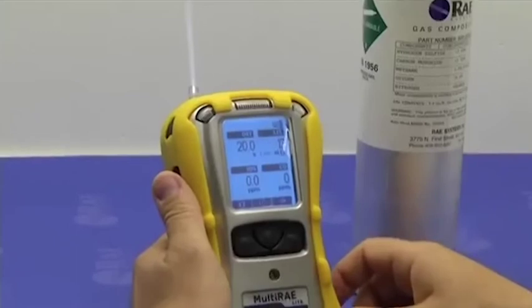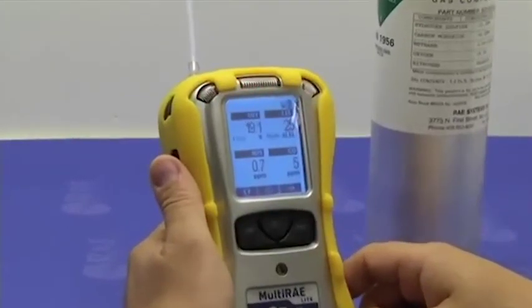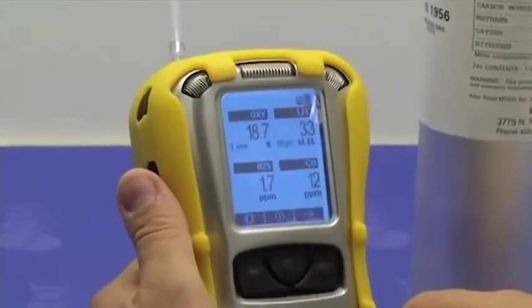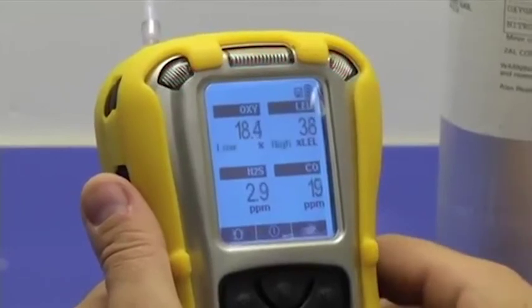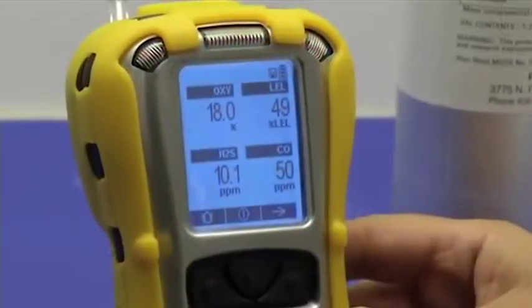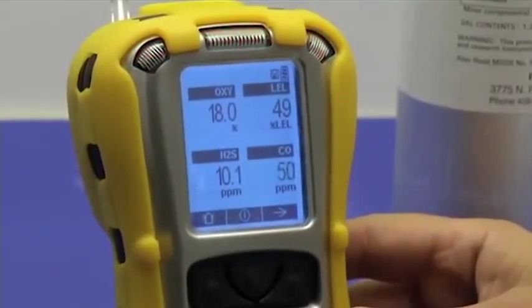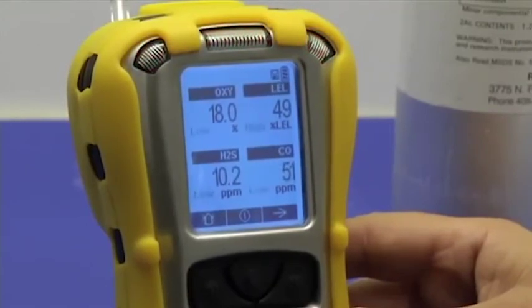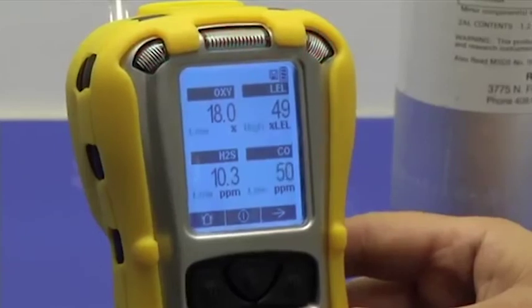Once again, my goal is to make sure the instrument goes at least into a low alarm on all the 4 sensors. Now we can see that all the sensors are in alarm and all the alarms are functional on the instrument. So it means it passes the bump test successfully.